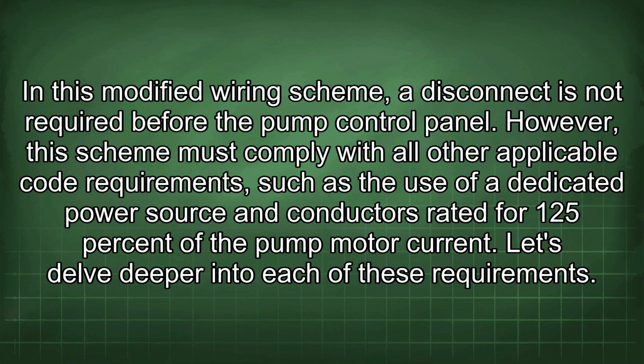In this modified wiring scheme, a disconnect is not required before the pump control panel. However, this scheme must comply with all other applicable code requirements, such as the use of a dedicated power source and conductors rated for 125% of the pump motor current. Let's delve deeper into each of these requirements.